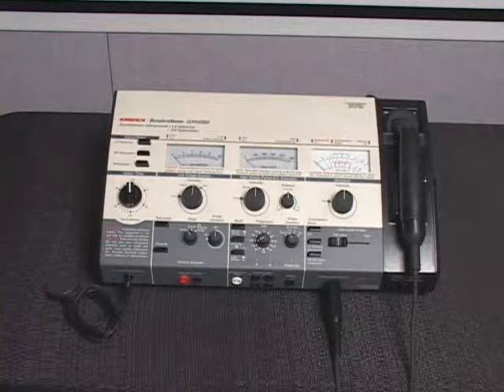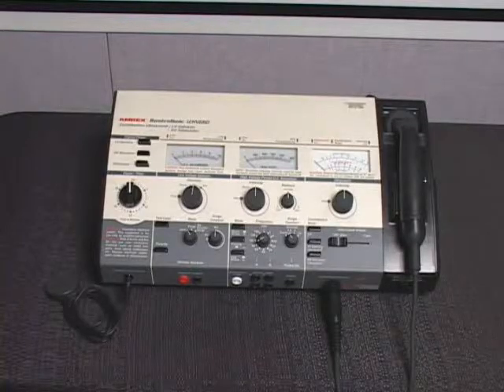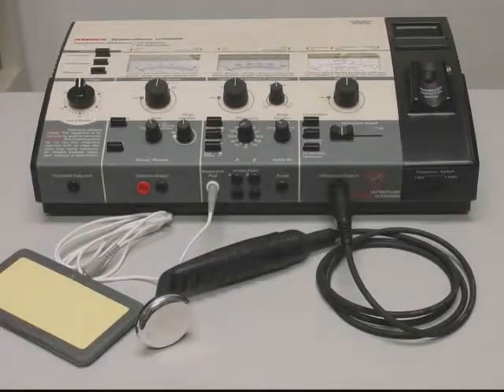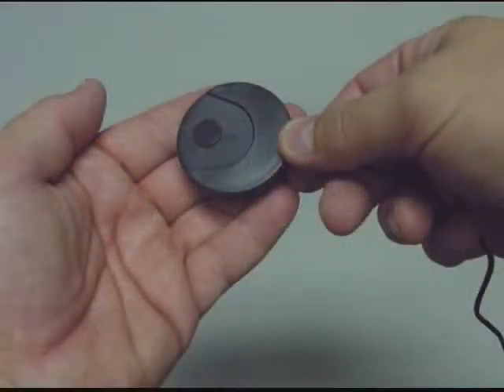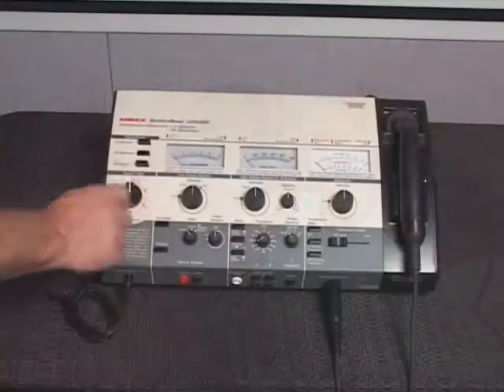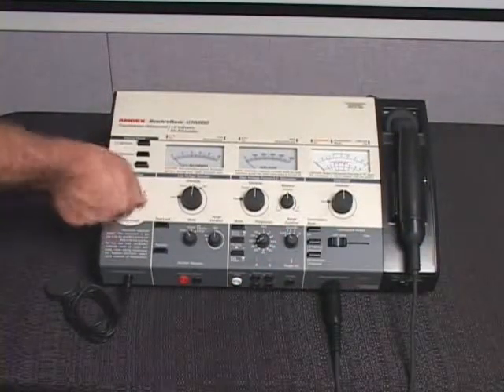Prepare the probe or pad electrodes and dispersive pad electrode and apply them to the patient. Electrical stimulation travels between the probe and dispersive pad or pad electrodes and dispersive pad. The pad electrodes may be held in place by means of retention straps or weight bags. Hand the patient treatment stop switch to the patient and explain its function. Turn the power timer knob and set it to the desired treatment time.